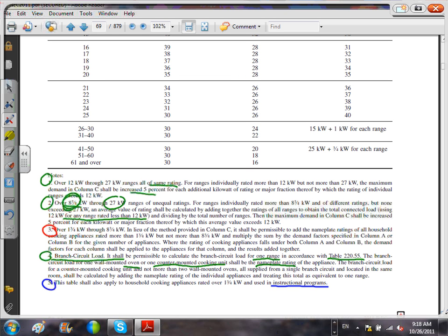They also have an exception here. They say if you are an electrician and you decided to group 2 ovens and 1 countertop unit in one branch circuit, how would you do that? You take a branch circuit like here, guys, pull it up to a J box right in here. From the J box, take one tap, no overcurrent device, feed oven 1, another tap, oven 2, and a third tap feeding a countertop cooking unit.